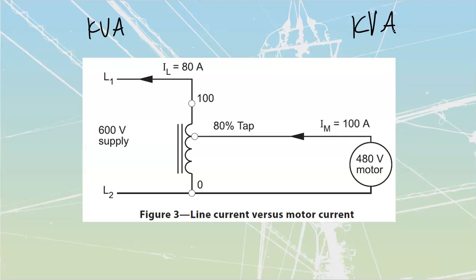So if I'm going to reduce a voltage, I can take my 600 volts and do 600 volts at an 80% tap. I can literally just go 600 times 0.8, which drops me down to 480 volts over here. So this motor, if it was a single phase motor, would be seeing 480 volts across there. Then I can figure out my amount of current through there.